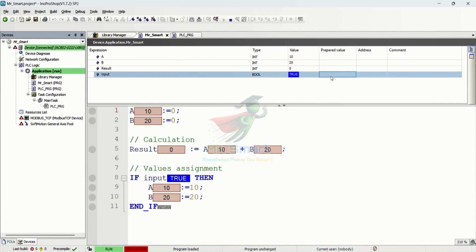Every scan begins by resetting A and B to 0. Every scan calculates result before updating A and B. Every scan locks in result as 0. That's why result always stays 0. Not because the math is wrong, but because the timing is wrong. This is the silent trap of structured text. The PLC is incredibly fast, but completely literal.